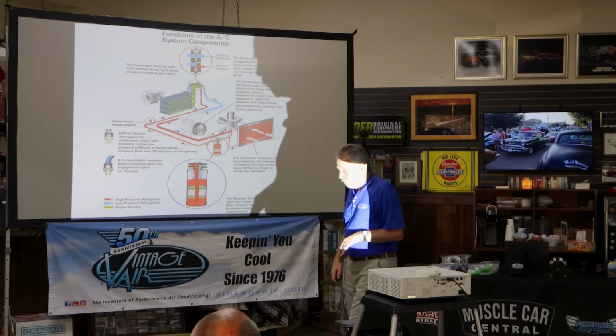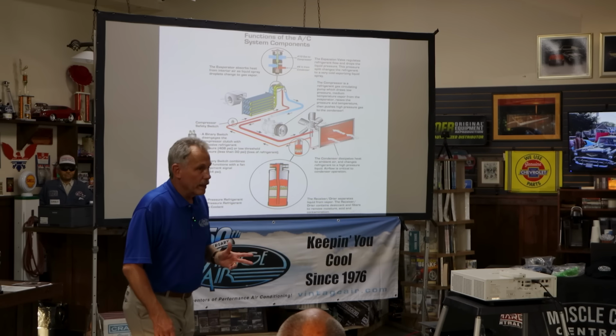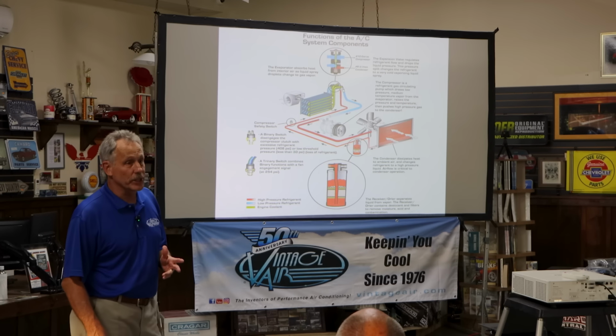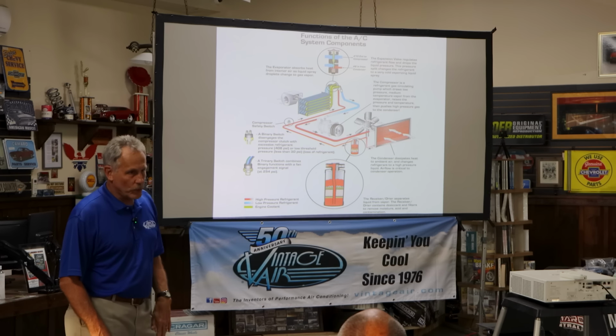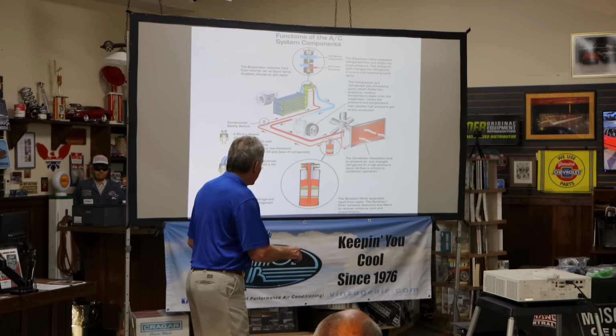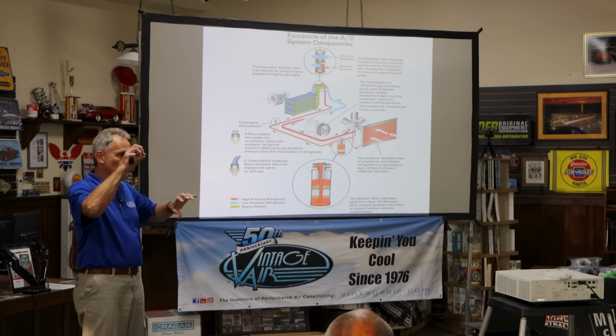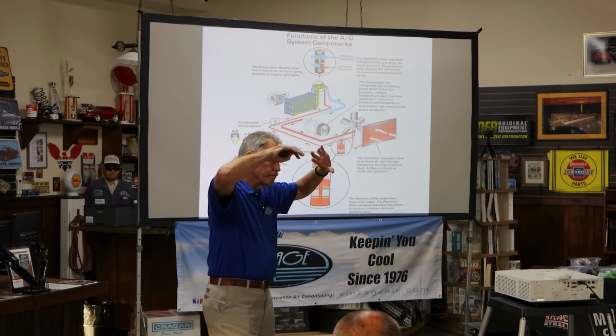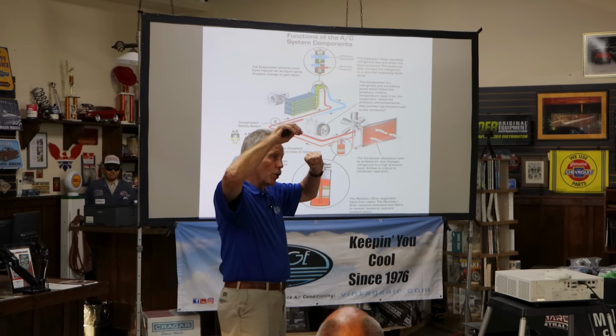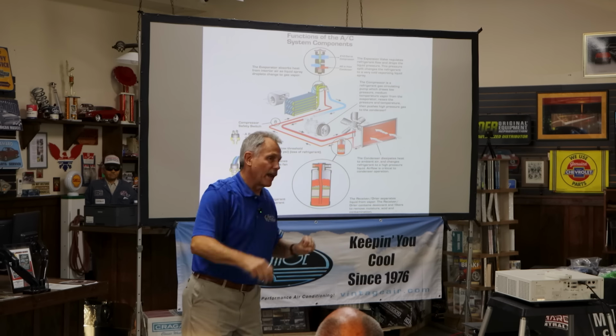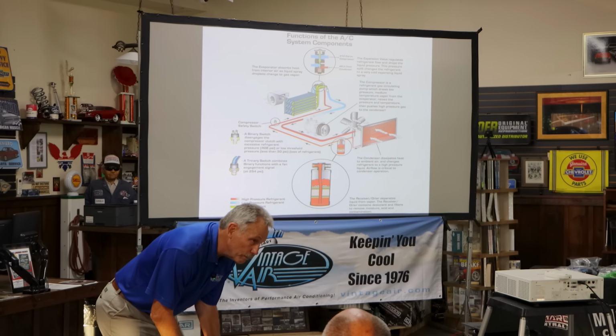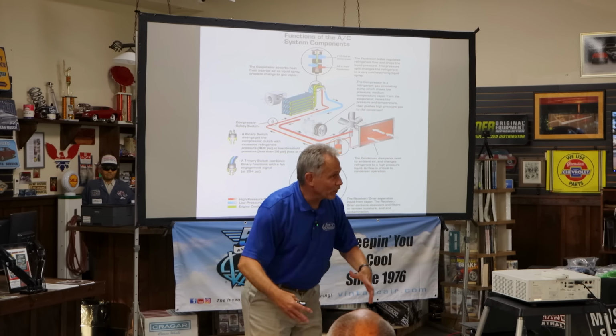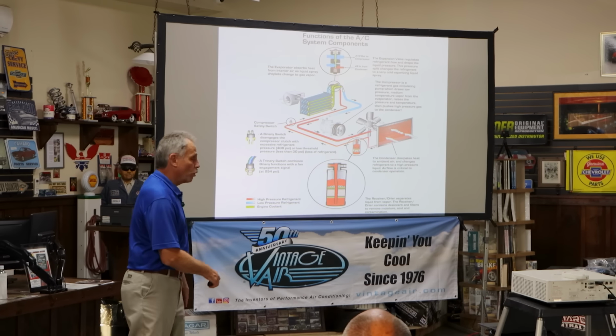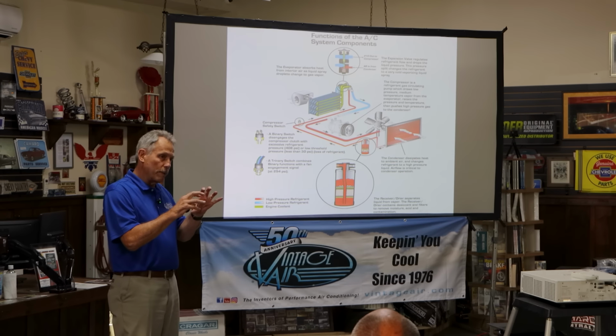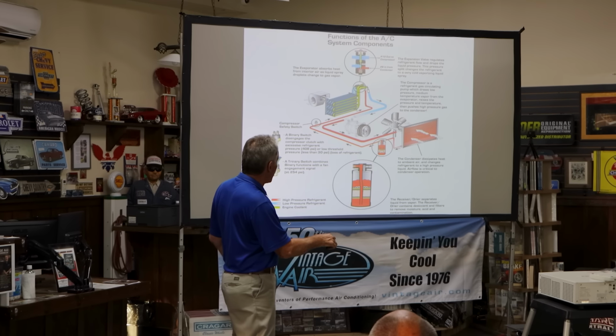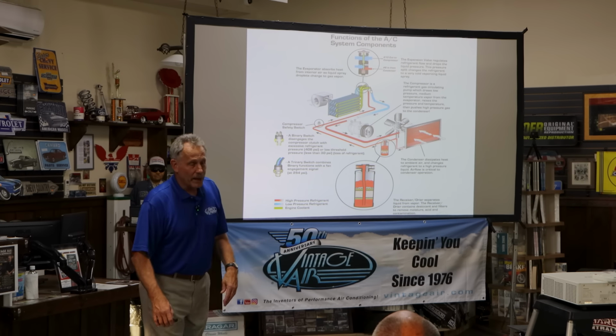We've got moisture in that coil, and the air is getting cooler. I'm sure everybody's heard about freeze up on your AC. What happens when an AC system freezes up is if the coil temperature gets down below 32, you've got all those droplets of moisture on the fins, and now they start to become ice crystals, because below 32 those droplets freeze into ice. If you've ever built a snowman, what happens when you take a little snowball and start rolling it around? It gets bigger, right? Same thing happens in your coil. As those crystals start to form, there'll be more and more, and it can finally turn into literally a block of ice. At that point, the system's froze up.